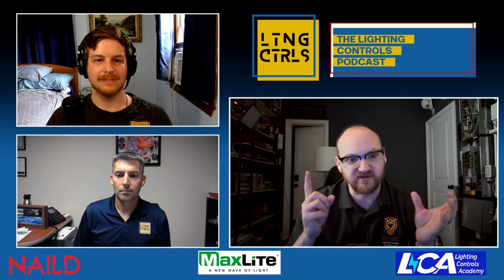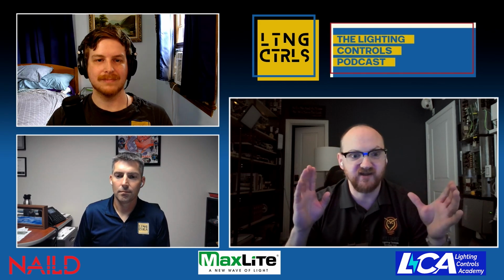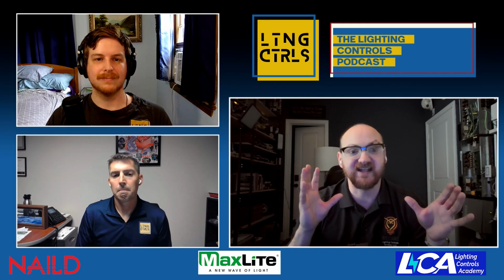My primary manufacturer, I'll give them a shout out, Watt Stopper. They have the ability with their handheld remote on the DLM side, if they've got a bunch of sensors on their in-room bus, to tell all sensors to go into test mode, or select just one sensor. That one sensor, if it times out, will control all the lights regardless of anything else. So what's great is I can keep people away from me and check one sensor at a time, put it into test mode, and regardless of the time delay, say 20 minutes, it'll go to 6 seconds and turn the lights off, regardless of movement triggering the other sensors on that IRB.